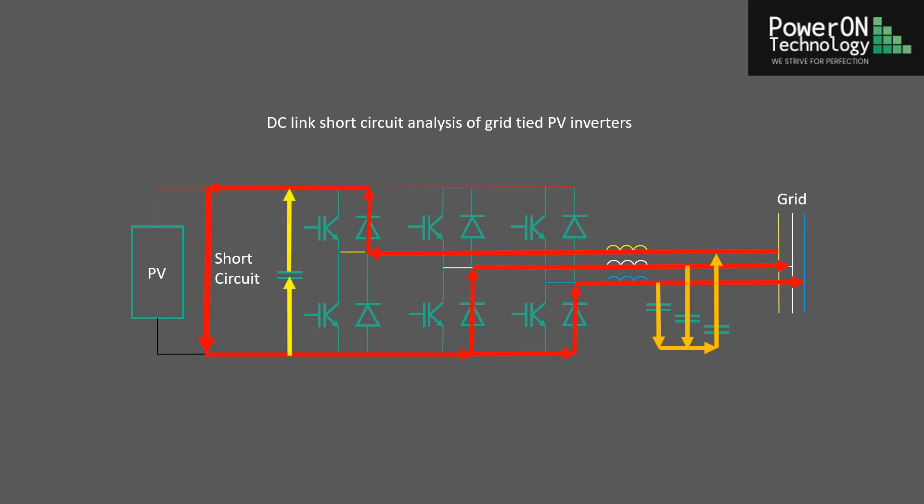The second part of the fault current is the discharge from the DC link capacitor directly into the short circuit. This capacitor bank is usually quite large, so the peak current is likely to be quite high, but it does not last long. However, the damage due to this discharge current can be quite severe.